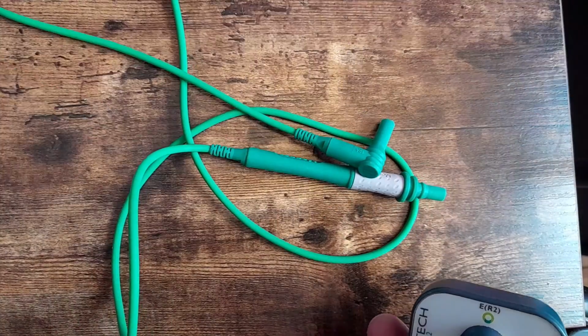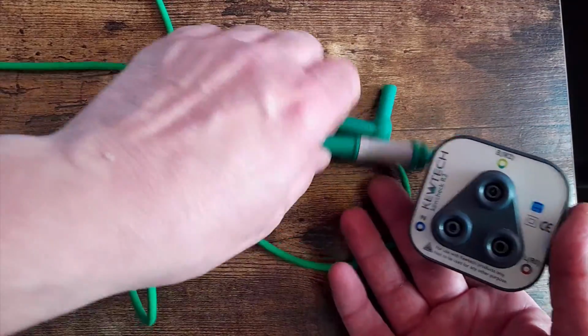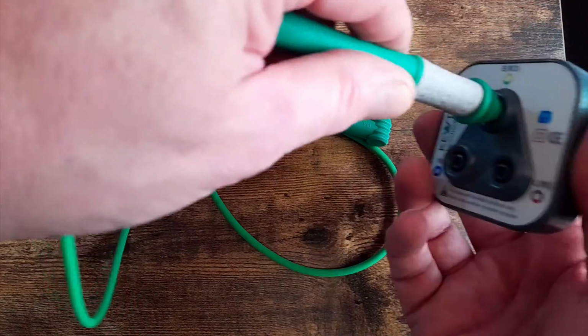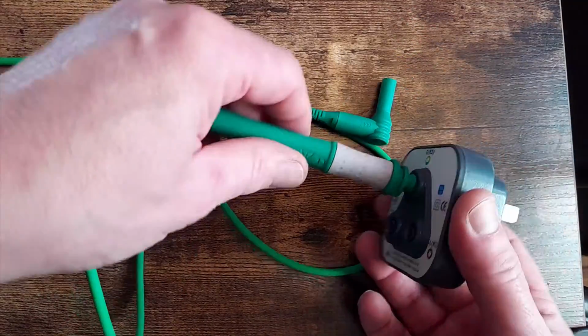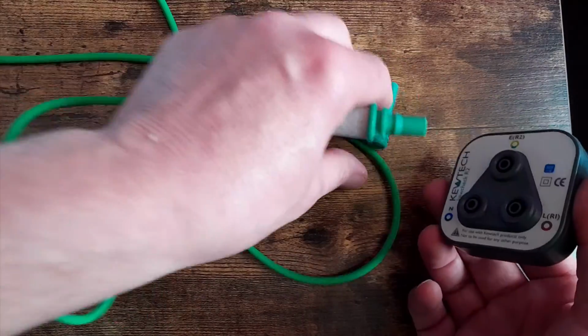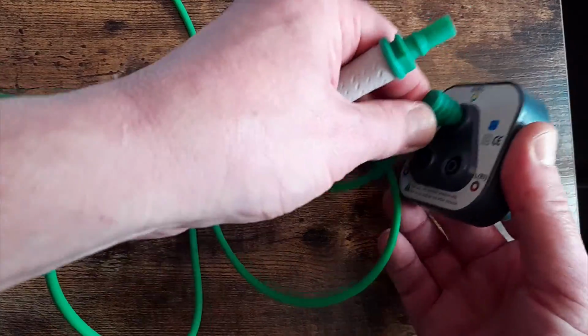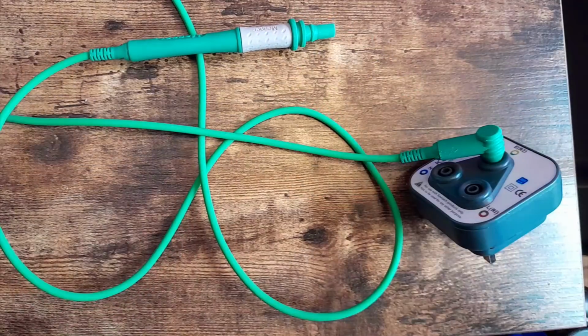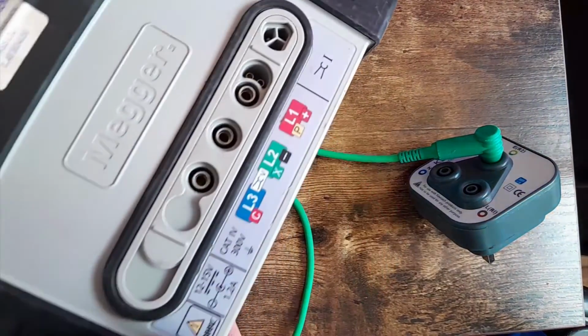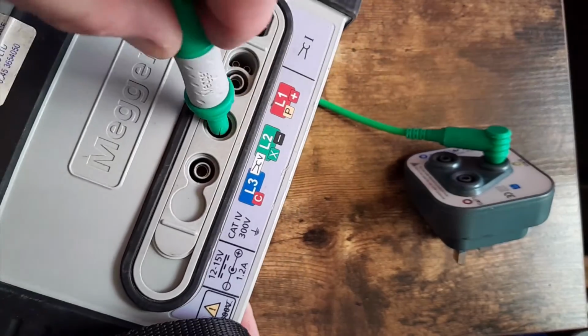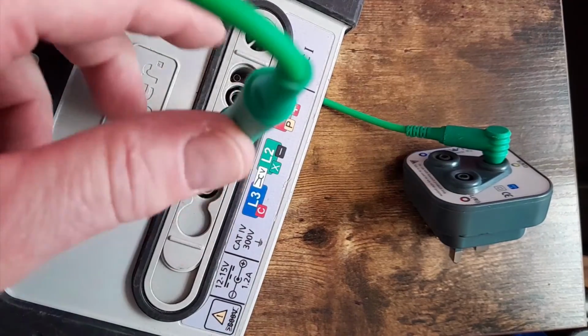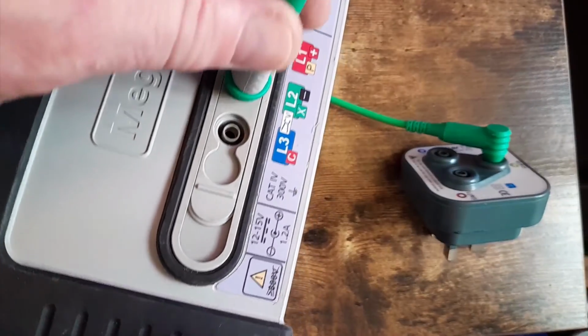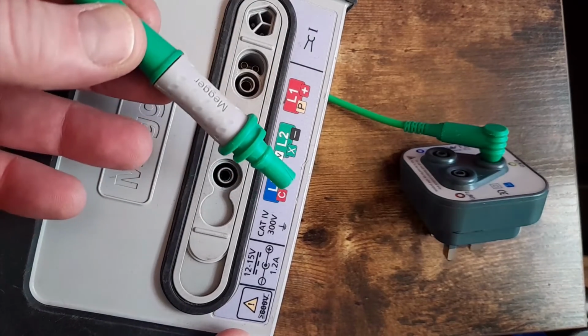Most multifunction testers come with a plug set. You do have to be careful with your leads though. For example, these are some leads of my Megger, and they'll only fit into this adapter one way. If you try and put the probe in that way, it's not making a connection. So you have to put that end into the adapter, and the shorter end actually goes into the Mega. So it's the opposite way around to what you would normally do it. Do check that your leads are making a good connection.